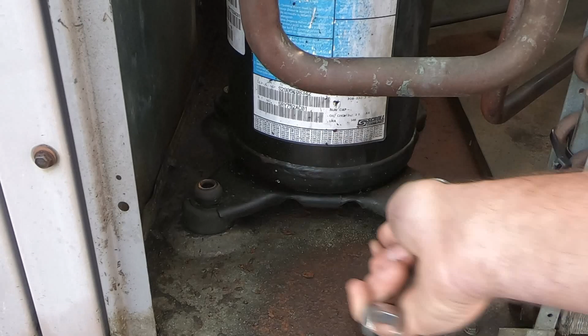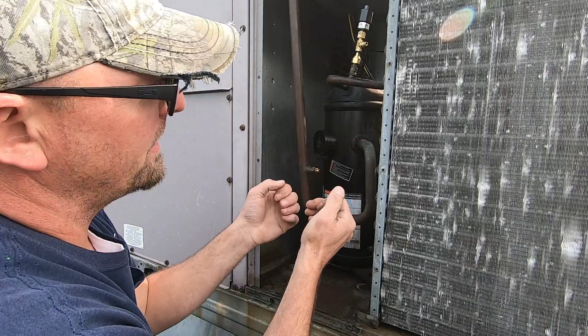Here's a little trick I've learned over the years. I always take the bolts out, and you can see my suction line and discharge line are both on this same side of the compressor. So I free it up and give the compressor a shove. That way when I heat these lines up, it's a lot easier to get these pipes out of the compressor, since the pipe naturally wants to move this way. So you heat it up and it should pull right out.